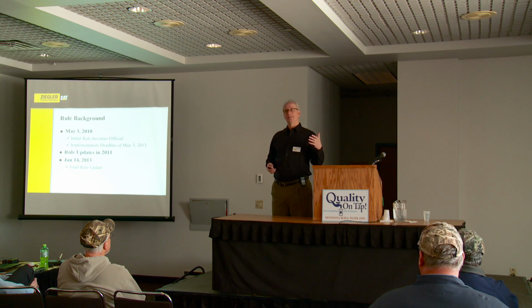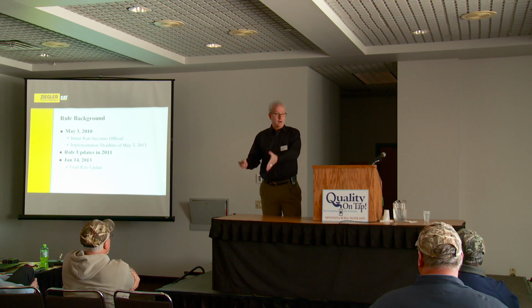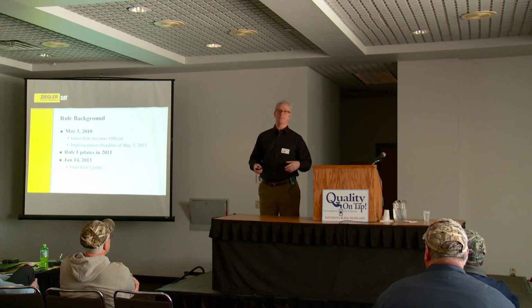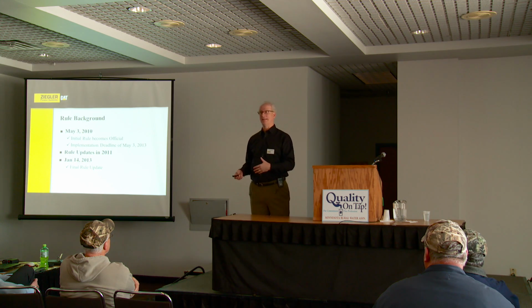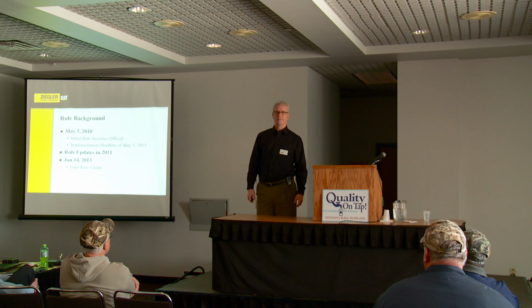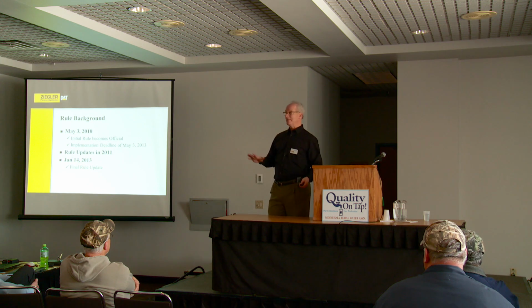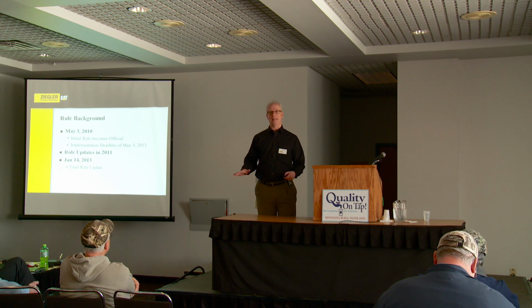There's all this stuff about new engines I talked about before. I guess the thing I didn't make clear is that the EPA has sort of said you have to follow the rules that apply at the time you buy the engine, or the time the engine was made. So, okay, I bought an engine in 2006, and it's a Tier 2 engine. There's nothing in any of those new rules that says you have to go do anything to upgrade that engine. It's grandfathered in and met the rule. It's like, when does the EPA tell you that you've got to go into your garage to your 1970 Corvette or something, and put a whole bunch of emission control on it? That's my old Camaro I've got in the garage. So here's one where they did do that. This is something where we're going to have to go back into older engines and make changes.